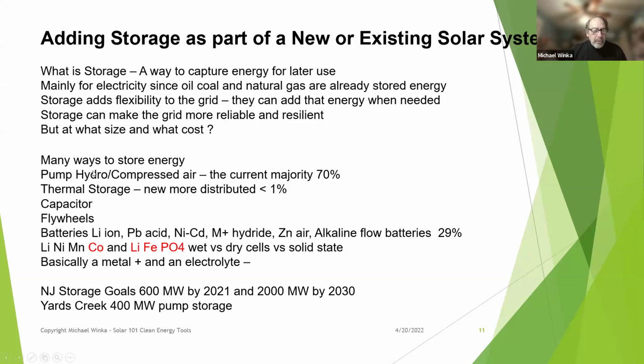area between large long-term storage and short-term storage. So batteries can fit the bill between very fast responses and somewhat long responses with their battery loads, but durations are 8, 10, 12, 16 hours as opposed to pump storage, which can do days. So there are different types of batteries, a whole bunch of different chemistries. You may have heard the cobalt issue about mining cobalt. So that's lithium, nickel, manganese, cobalt, but they're being replaced by lithium iron phosphate, which has lower efficiency, but better power density, greater thermal response, not as much of the problems with nickel metal cobalt.